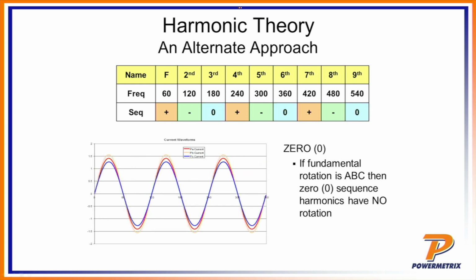And then finally, 0th level. These are called triplens or thirds. These are a real big problem, simply because of the fact that all 3 phases, the returns are in sync. A lot of times, the reason that's a problem is that those currents end up going back through the ground conductor.